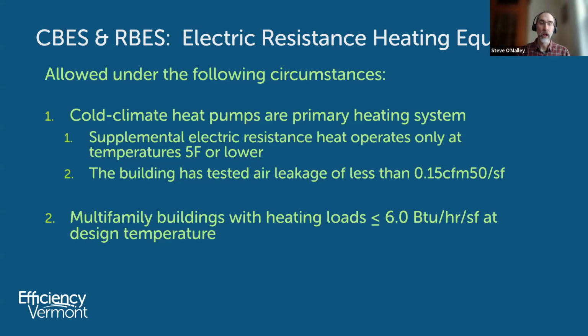Another instance where electric resistance heating is allowed is, say you didn't even want to install cold climate heat pumps. I'm not sure how you do cooling, but if you wanted to heat your building with electric resistance only, you are allowed as long as you can hit this metric. It's multifamily buildings with heating loads that are less than 6 BTUs per hour per square foot at design temperature. So if you knock your thermal shell out of the park between R value and air leakage, you are allowed to heat your building solely with electric resistance, which could be a massive cost saving depending on what your approach is for providing cooling.